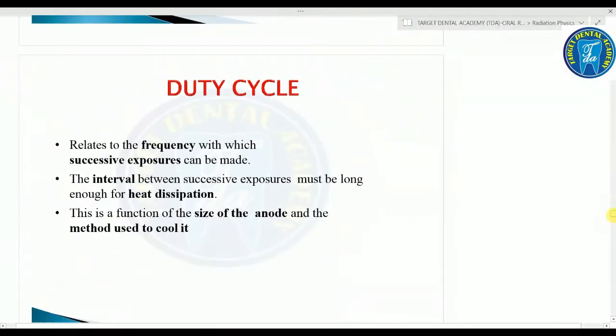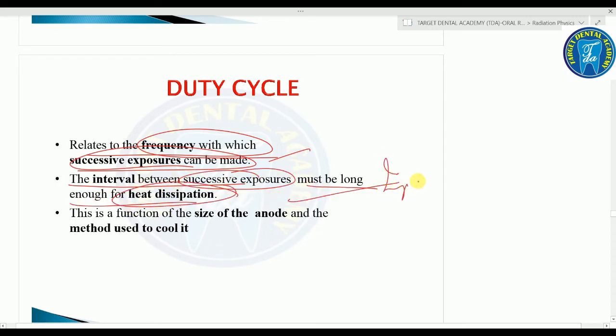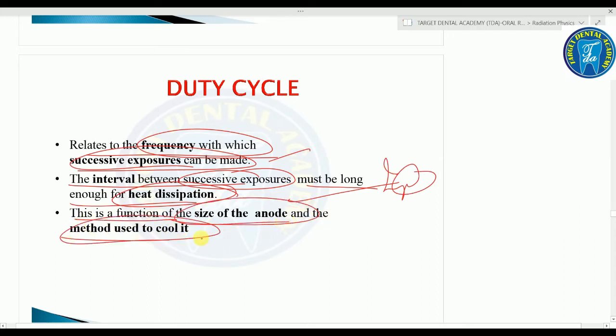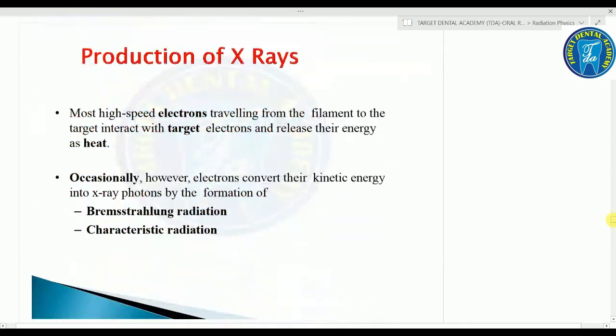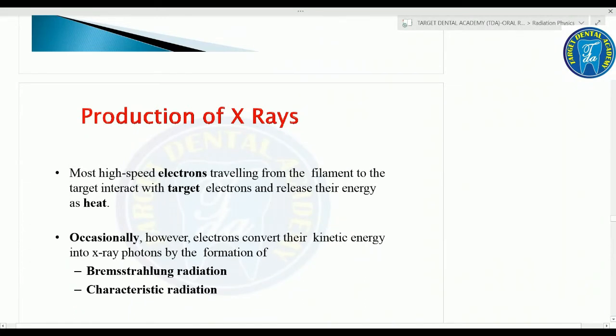The duty cycle relates to the frequency with which successive exposures can be made. The interval between successive exposures must be long enough for heat dissipation. This is a function of the size of the anode and the method used to cool it.